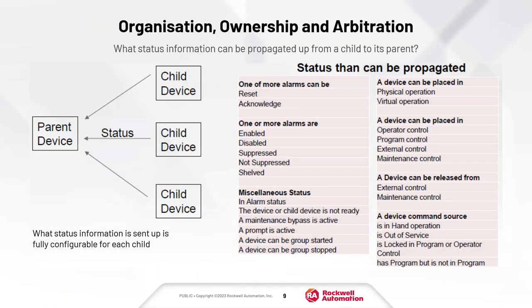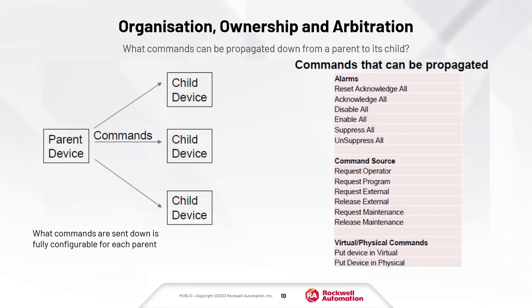What status information can be propagated using Organization, Ownership and Arbitration? You can see a list of all the things that can be propagated, but a key point is that it's highly configurable - at each level you have full control about what information is propagated up to the level above it. Similarly, for commands propagated down from a parent, you have full control about what is propagated from a parent down to a child at every level.